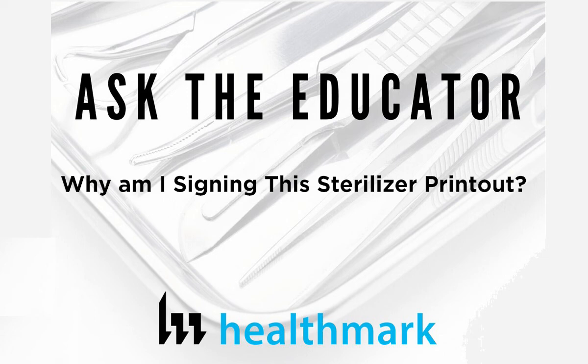And ensuring that they are holding within the time. So that 4 minutes is your sterilization time. A lot of people are like, oh, I thought it meant dry time. Nope, it's sterilization time. Dry time actually has nothing to do with it. Then your temperature, making sure that you hit the right temperature range, whatever you were set for, and that it's holding, and then that you're reaching your right pressure range.